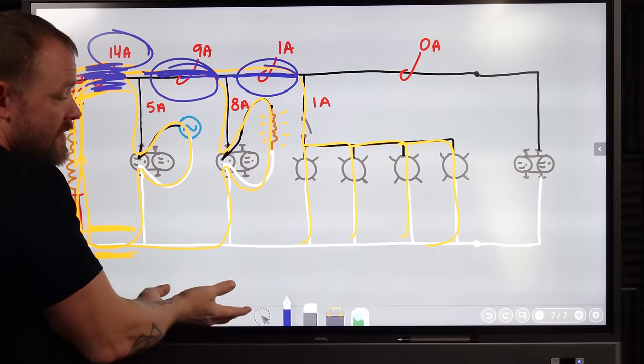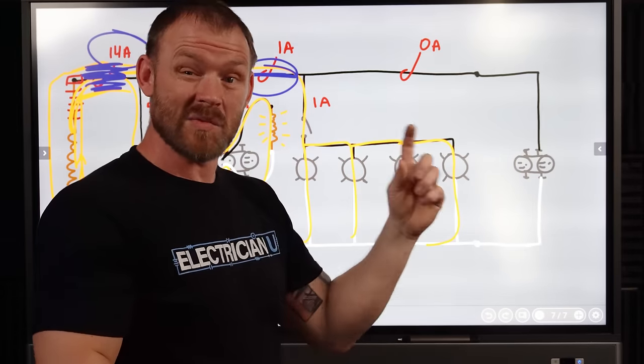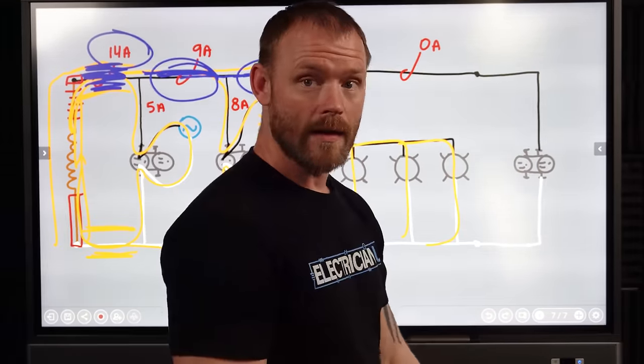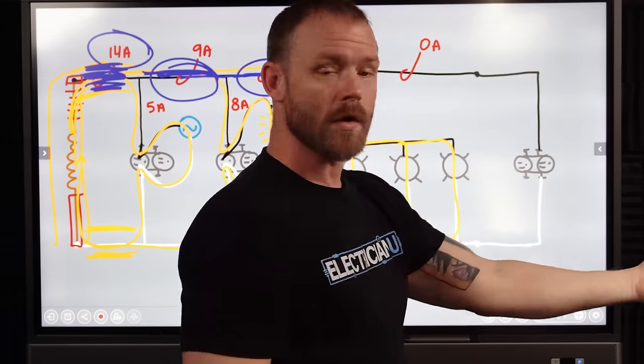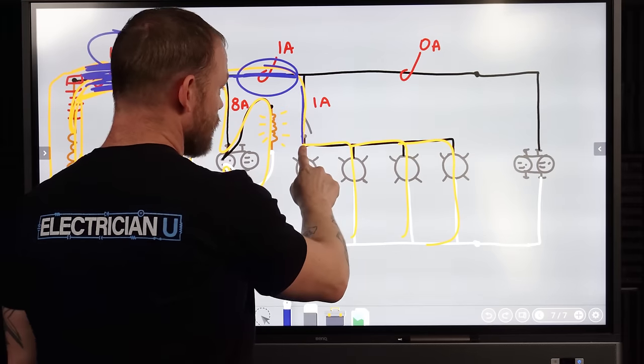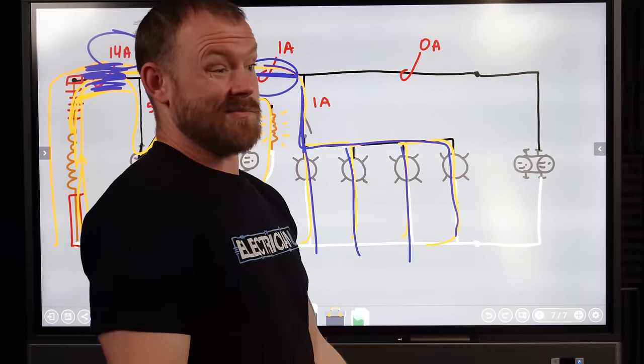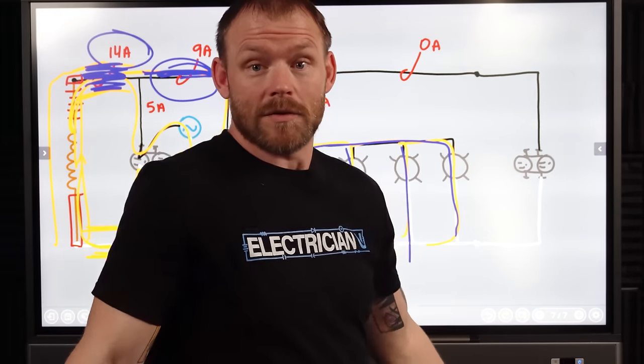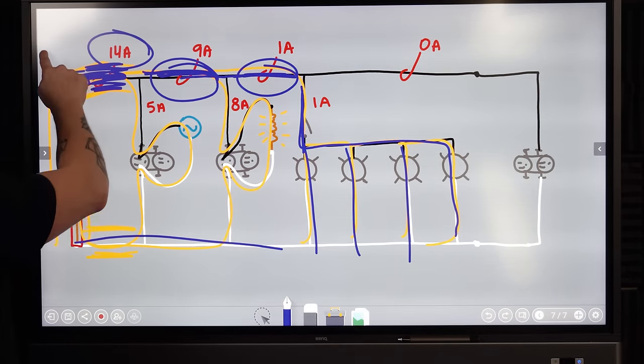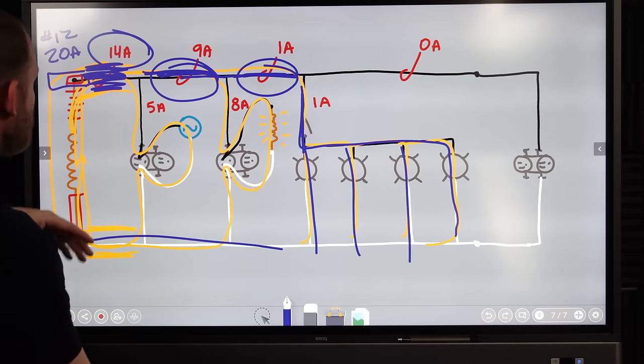That's why I would size the whole branch circuit to be 20 amps — because of this additive effect. But when I'm at the switch leg, even if there's another receptacle with nothing plugged in, there's still conductor over there with no current flow at all because it's in parallel. If I only worry about what's going on up at the lights, I could run that whole thing in number 14 — or even smaller. That's why we hook up to a 20-amp breaker and run number 12 on the main branch, and the neutral is also number 12.